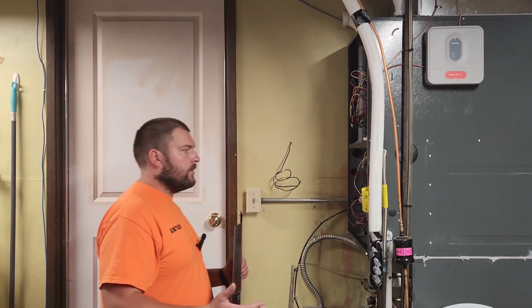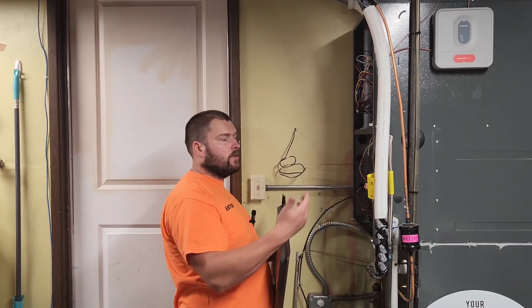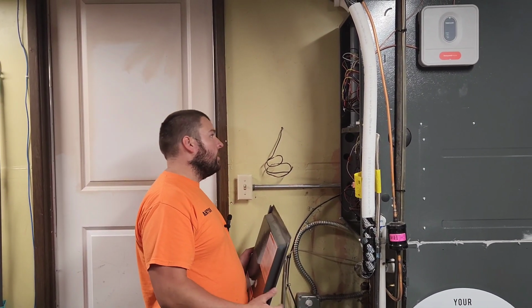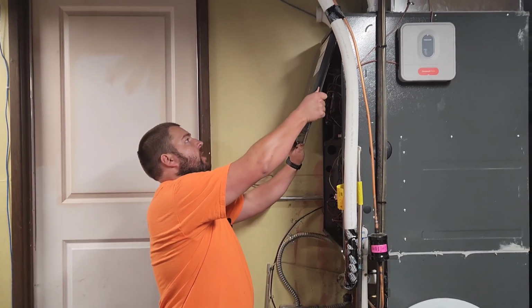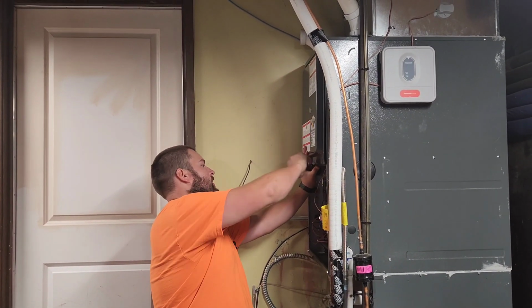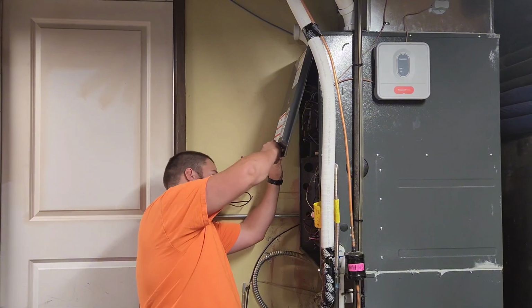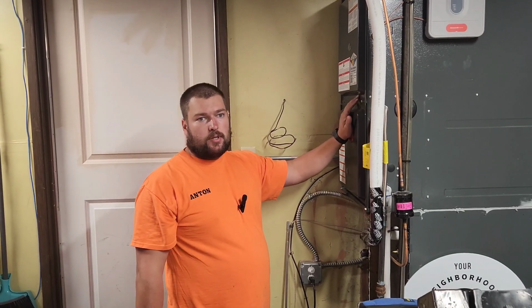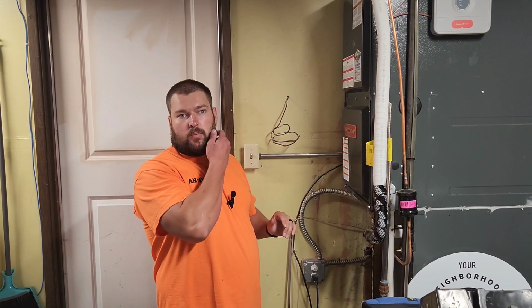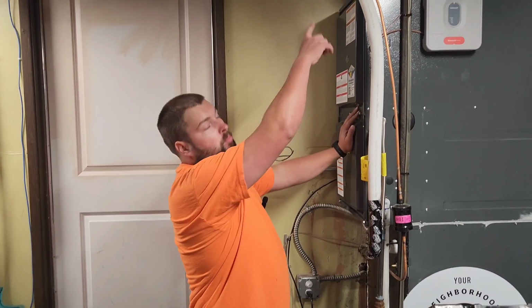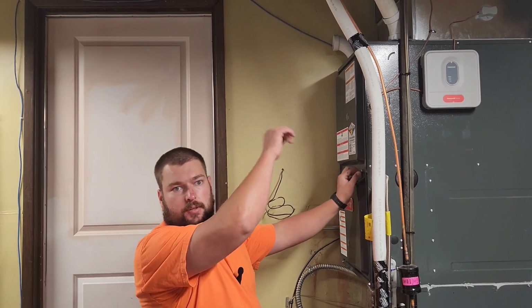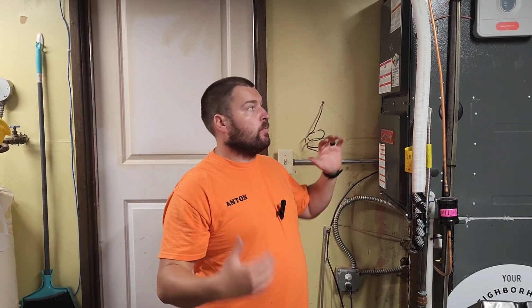After we've checked everything, checked all the gas connections, make sure you don't have a gas leak here or anything, we'll go ahead and put these doors back on, just because I don't really need to be in this furnace anymore. So last thing we want to check is the heat exchanger. We want to make sure that it's not compromised or has cracks, and we can do that with a combustion analyzer, where we drill a hole into the vent pipe and check your combustion, or a carbon monoxide walk-around test with a Fieldpiece meter, and we run this furnace for about 15 minutes.